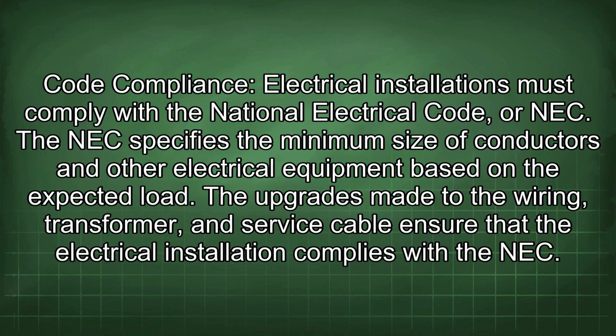Code compliance. Electrical installations must comply with the National Electrical Code, or NEC. The NEC specifies the minimum size of conductors and other electrical equipment based on the expected load. The upgrades made to the wiring, transformer, and service cable ensure that the electrical installation complies with the NEC.